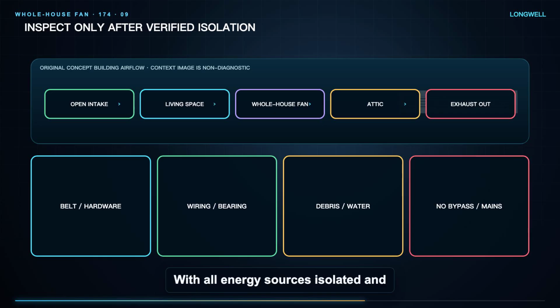With all energy sources isolated and stored energy handled, inspect for a displaced belt, loose hardware, rubbed wiring, seized bearings, damaged shutters, debris, water, overheating, or an obstructed wheel. Do not bypass a control or connect mains directly to prove a motor. Document evidence before replacing parts.